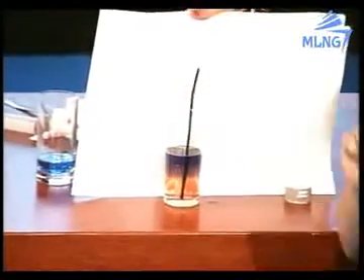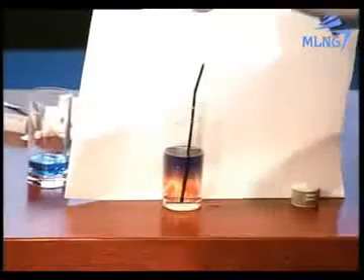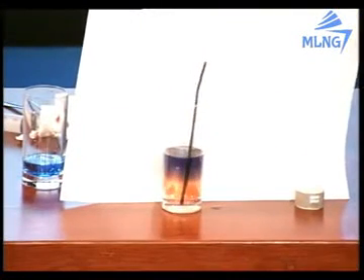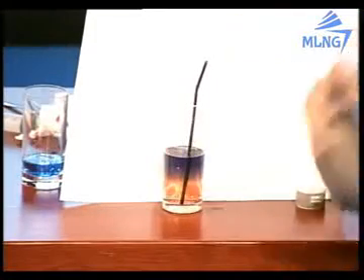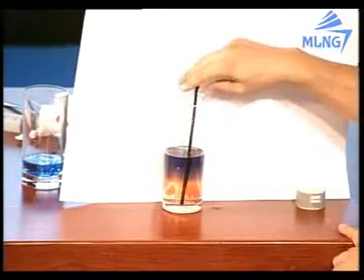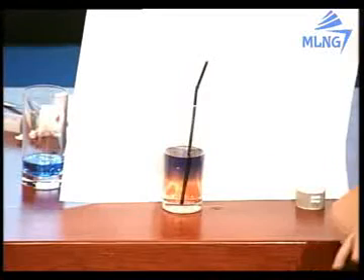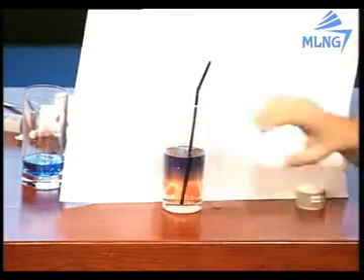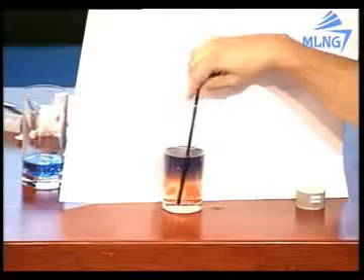And another way is recirculating pumps. We should switch on the primary pumps and recirculate. If we recirculate pumps, we mix the tank. So then, please zoom, okay? Then you will see that this tank will convert into a homogeneous tank. The 2 layers will disappear, okay, like this.